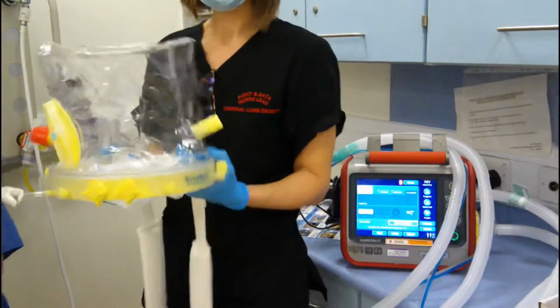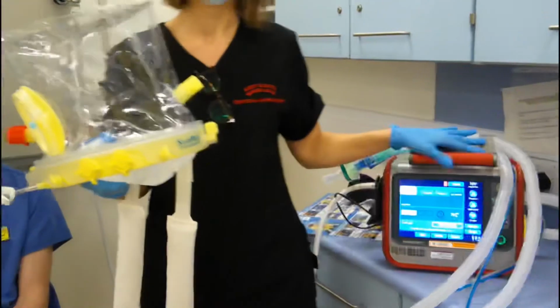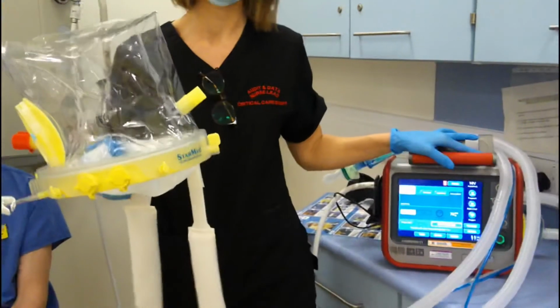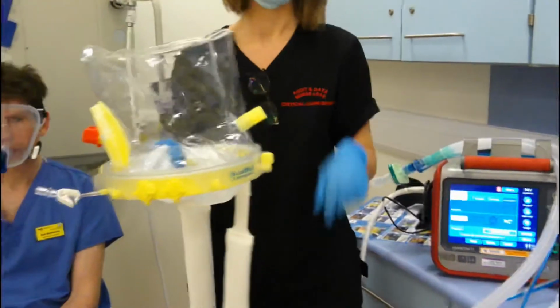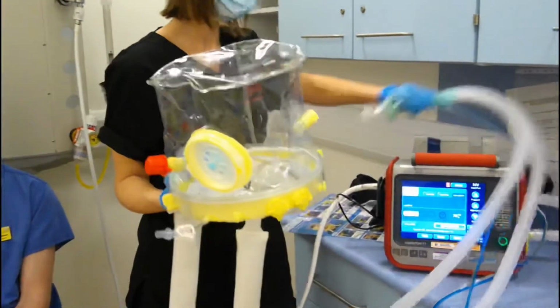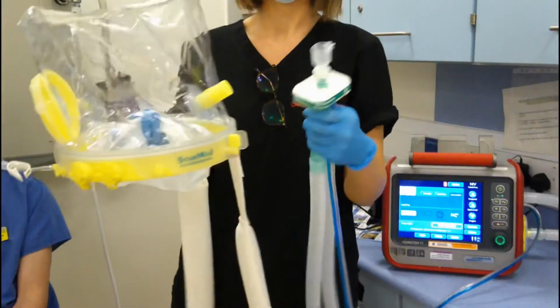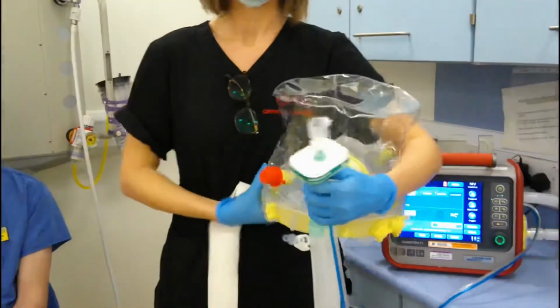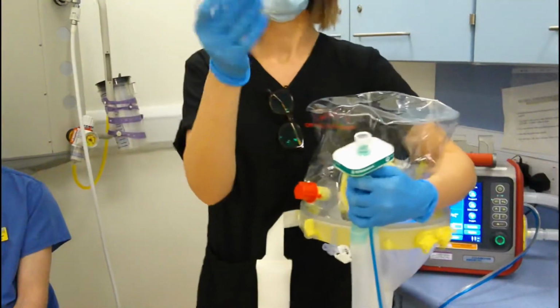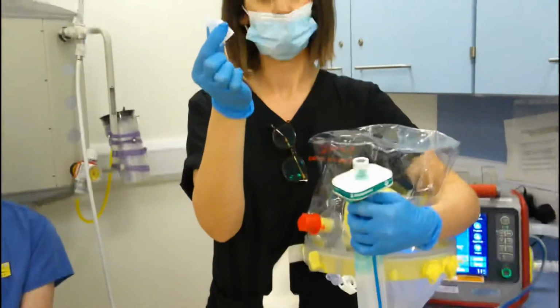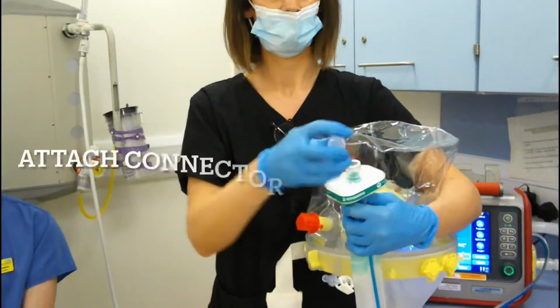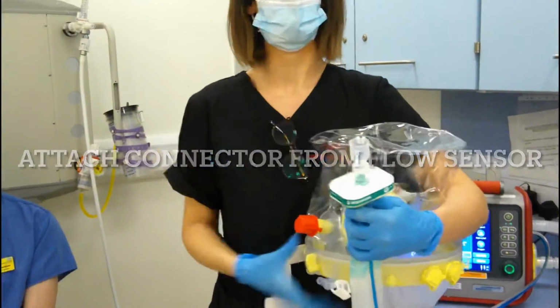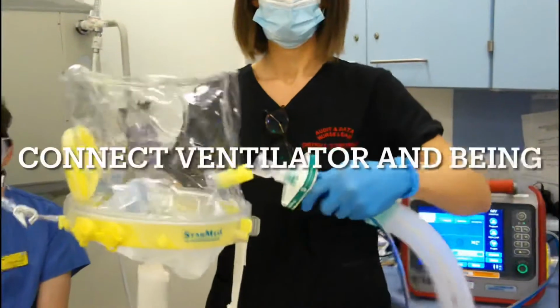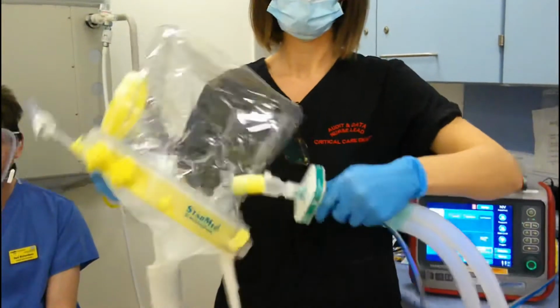So what we say to do is get the ventilator set up for non-invasive ventilation ready to go, attach it to the hood. Now for it to be compatible, what you need to have is the connector that comes with the flow tubing, the flow sensor tubing. This attaches to your HME and will allow you to connect it to the hood.